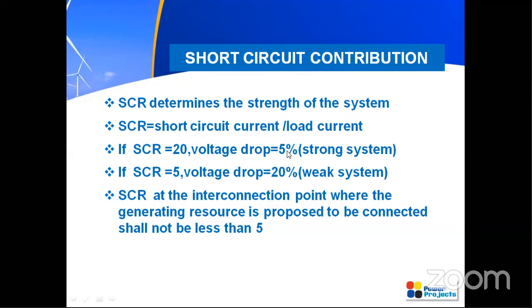From this voltage drop, you can easily get the point. Whether a system has a 5% voltage drop or a 20% voltage drop, which will be the strong system and which will be the weak system? Undoubtedly, the system with 5% will be a strong system and the system with 20% will be the weak system. So we can conclude that an SCR with greater value will be a strong system and an SCR with lesser value will be a weak system. That's what I'm trying to say.